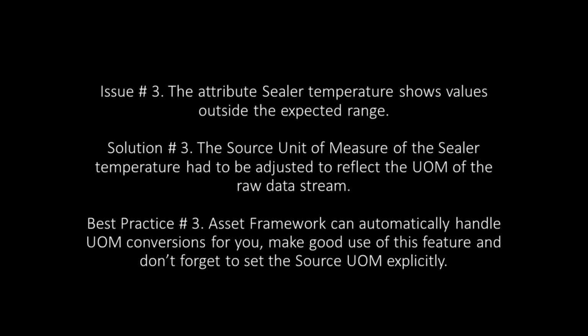Now, the best practice here is that AF can automatically handle units of measure conversions for you. However, in order to make good use of this feature, you need to specify your units at all points so you don't get trapped by using the default, which in our case was wrong.